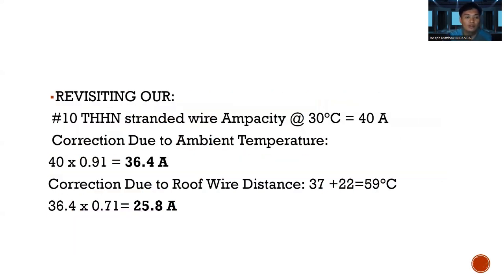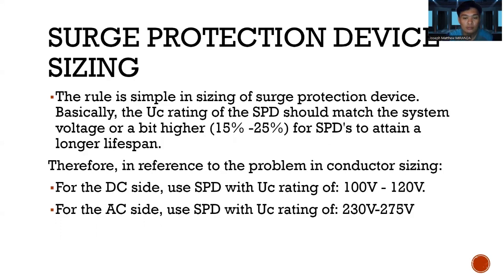So, revisiting our number 10 THHN stranded wire, ampacity at 30 degrees Celsius is equals to 40 ampere. Correction due to ambient temperature: 40 times 0.91 is equal to 36.4 ampere. Due to the roof wire distance, 37 plus 22 is equals to 59 degrees Celsius. So 36.4 times 0.71 is equals to 25.8 ampere.